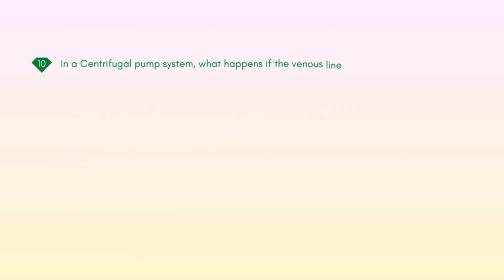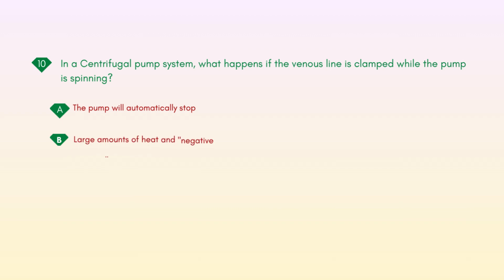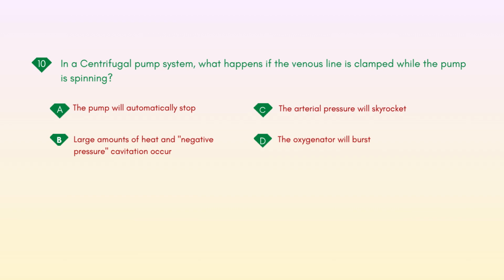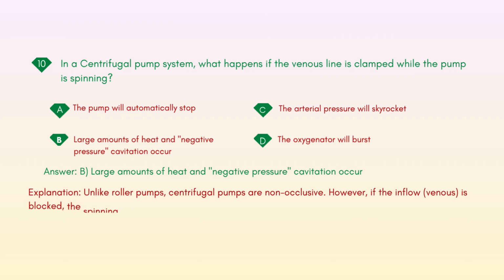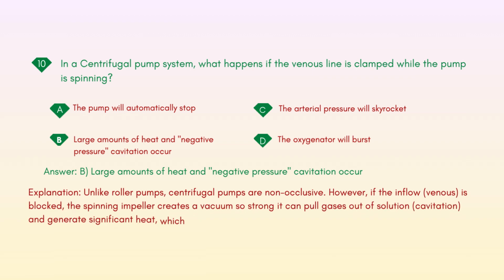In a centrifugal pump system, what happens if the venous line is clamped while the pump is spinning? A. The pump will automatically stop. B. Large amounts of heat and negative pressure cavitation occur. C. The arterial pressure will skyrocket. D. The oxygenator will burst. Answer: B. Explanation: unlike roller pumps, centrifugal pumps are non-occlusive. However, if the inflow, venous, is blocked, the spinning impeller creates a vacuum so strong it can pull gases out of solution, cavitation, and generate significant heat, which can damage the pump and blood cells.